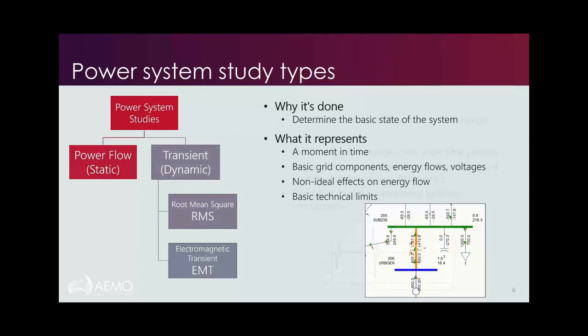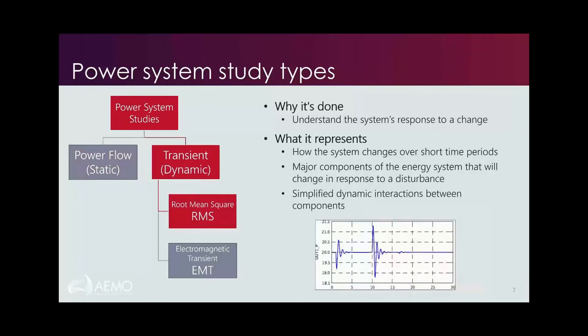Moving beyond static simulations, we can also perform transient or dynamic simulations to understand how the system responds to a disturbance or change, looking at the immediate aftermath over very short periods — maybe a couple of seconds up to a few minutes. We need to model major components of the energy system that change in response to a disturbance, primarily generator models and their control systems. The most common method is RMS — root mean square — which is essentially a mathematical simplification of the power system physics, meaning it runs very quickly on a computer, though with some assumptions and simplifications.